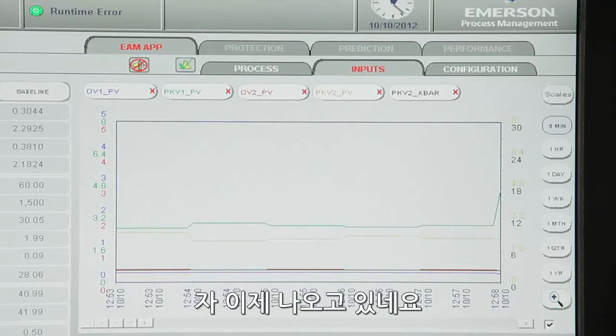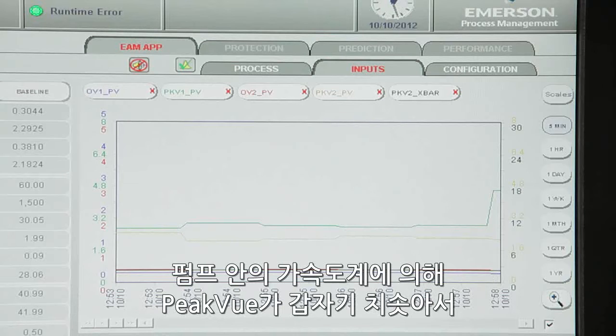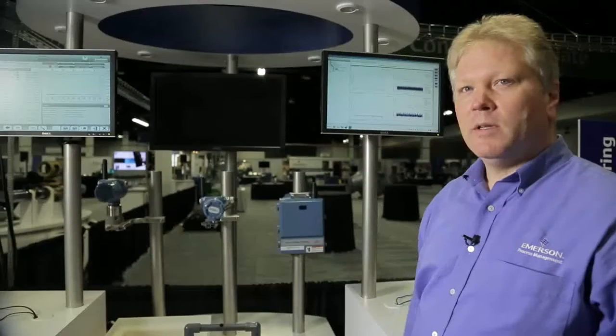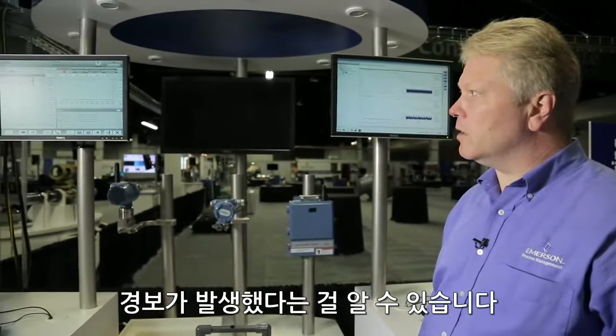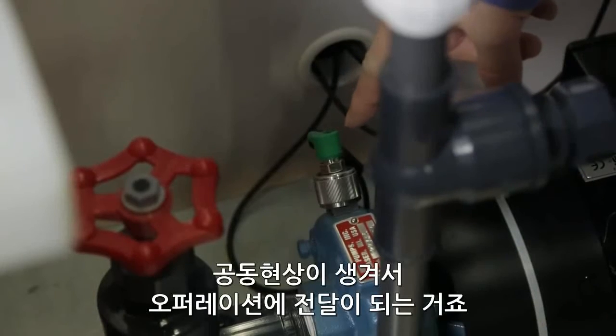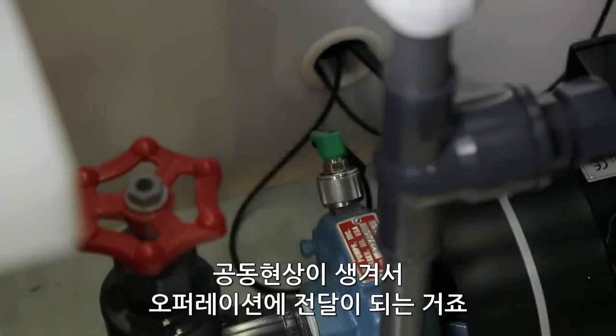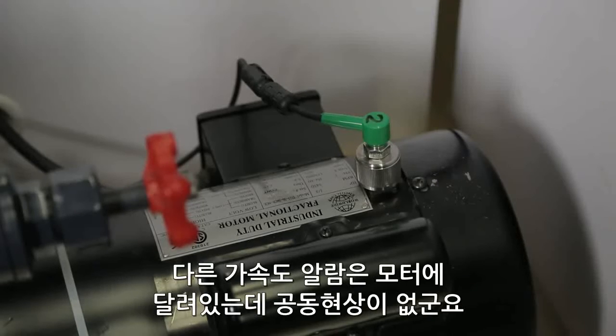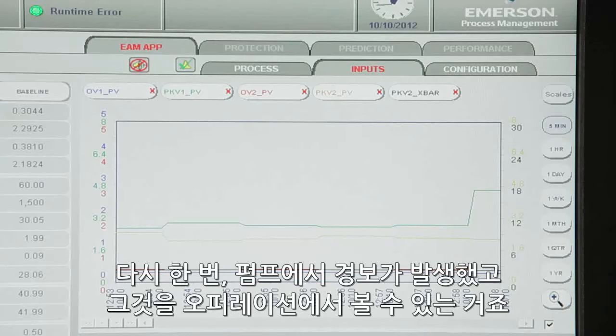And there we are. We now have the accelerometer on the pump for PeakVue that has actually spiked up, indicating to us that we have an alarm, that we've been cavitating the pump, so operations receives that. The other accelerometer was on the motor, that didn't cavitate. So again, the alert is on the pump, and we see that from operations.